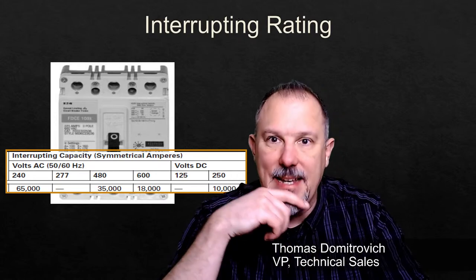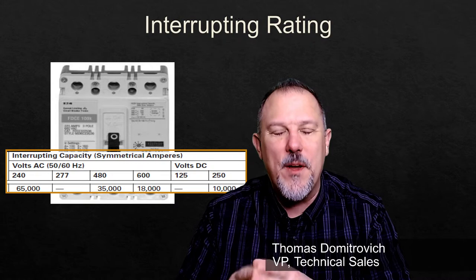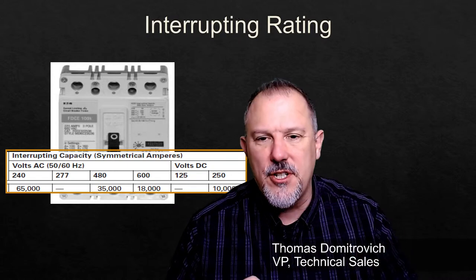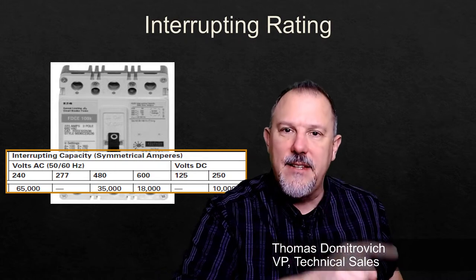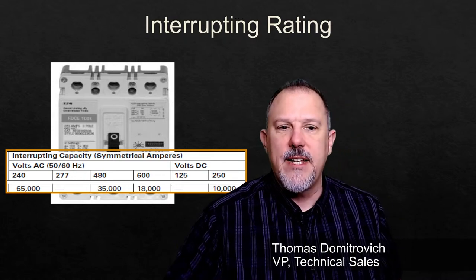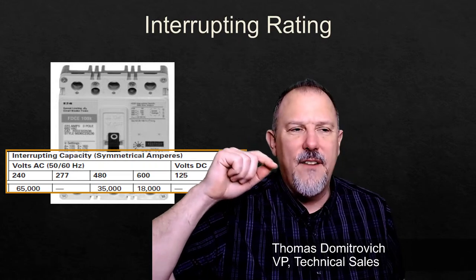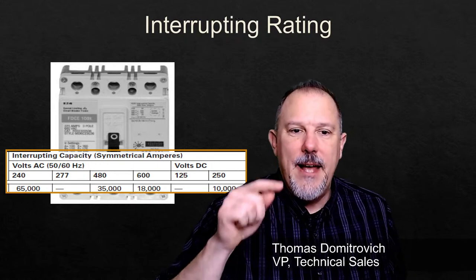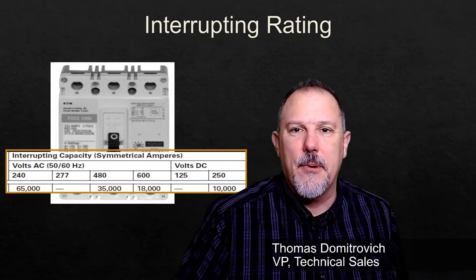So, a common mistake. In fact, I had a guy send me an email who was frustrated with his inspector. And he goes, Tom, you're an IAEI member, International Association of Electrical Inspectors. You're a member of that organization. You need to talk some sense into this electrical inspector. He goes, I have one of our circuit breakers that can interrupt 65,000 amps, and I've got only 45,000 amps, or 42,000 amps, whatever it was, in the 40s. And I have a 65K breaker, and he red tagged it and said I have a problem with my installation.